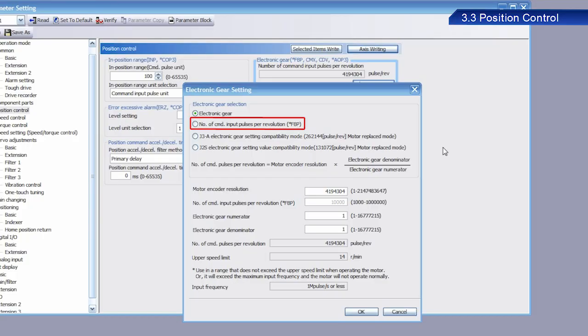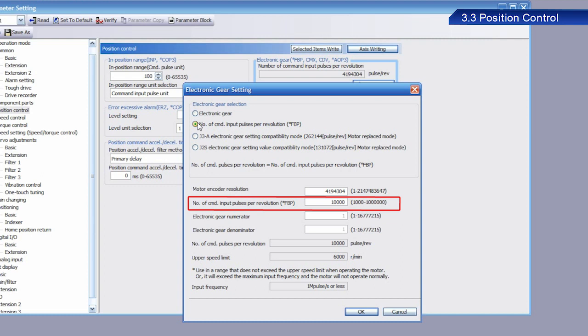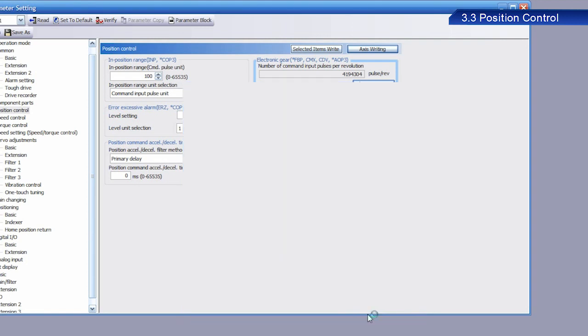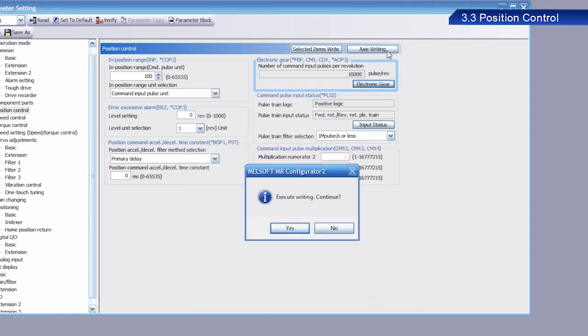Select number of command input pulses per revolution instead of electronic gear. Enter a value of 10,000 for the number of command input pulses per revolution setting. This sets the servo amplifier to divide each motor rotation into 10,000 pulses. After you have finished setting, it must be written into the servo. Once the dialog box appears, click Yes.